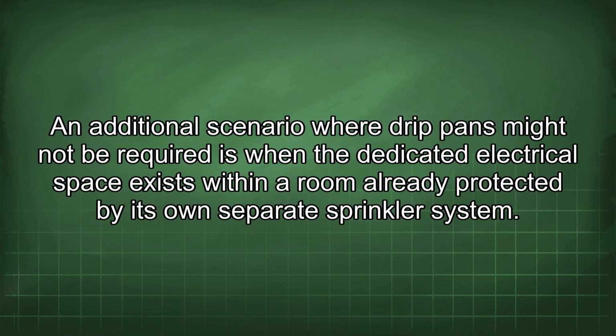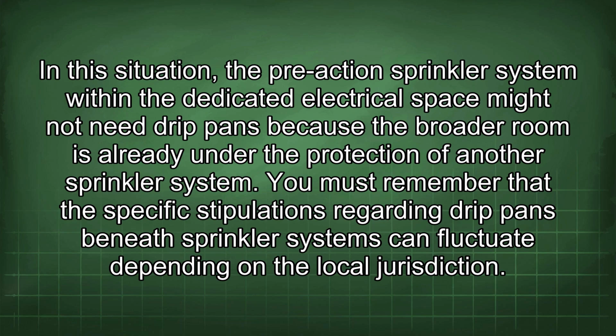An additional scenario where drip pans might not be required is when the dedicated electrical space exists within a room already protected by its own separate sprinkler system. In this situation, the pre-action sprinkler system within the dedicated electrical space might not need drip pans because the broader room is already under the protection of another sprinkler system.